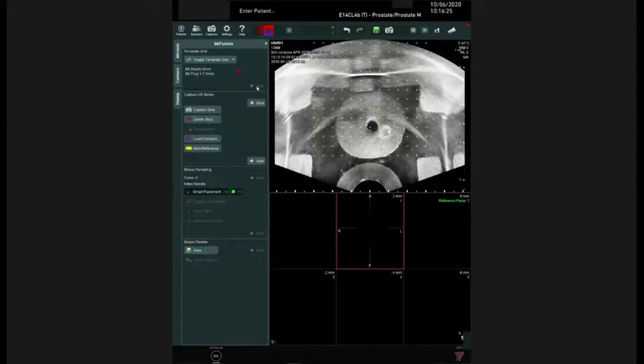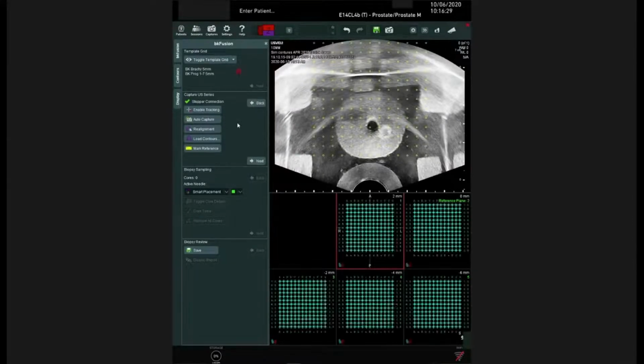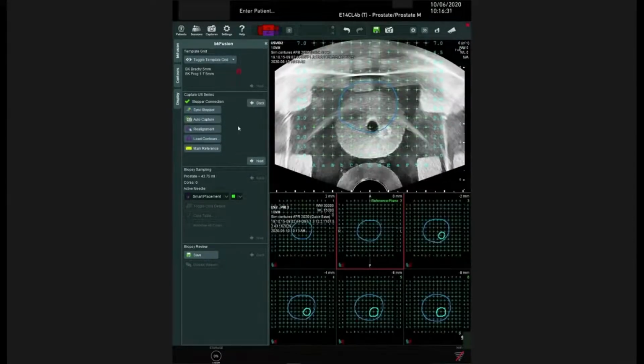Now the first step is completed. The next step is to fuse the MRI contours with the live ultrasound image. The first thing to do is verify that we have a stepper connection. The USB cable from the stepper should be plugged into the BK system. If there is a green check mark like you see here, then we have a good connection. If there is a red X, then you need to check the connection with the stepper.